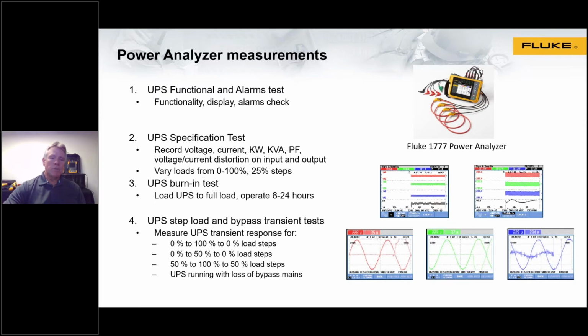Next step would be a burn-in test. So load the UPS to full rated load, again, via load bank, and then operate from 8 to 24 hours. And what you're looking at, again, is to show that it performs as per spec.